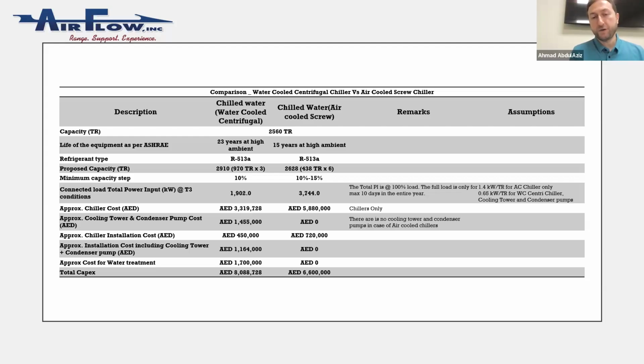We use the same refrigerant, 513A, so there are no differences in efficiency, because sometimes if you change from one refrigerant to another, you change the efficiency itself. So we use the same refrigerant. In water cooled, we use 3 chillers because you can get larger capacity. And in air cooled, we use 6. So you need to keep an eye on your space when you design. Do you have space for 6 chillers, 6 pumps, 6 pipes? Air cooled will be maybe 8 meters, 10 meters, compared to maybe 5, 6 meters as water cooled. So you need to keep an eye on the installation part as well.